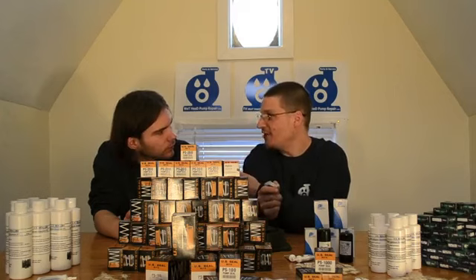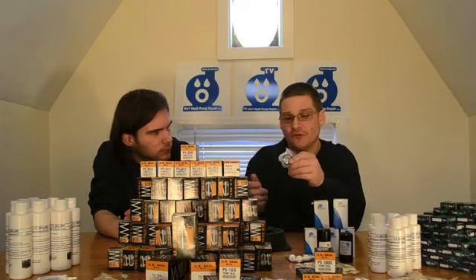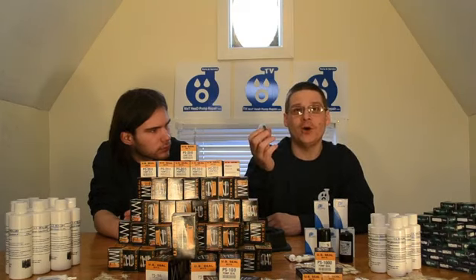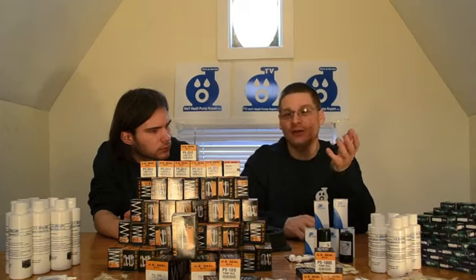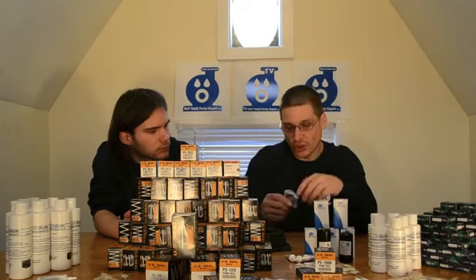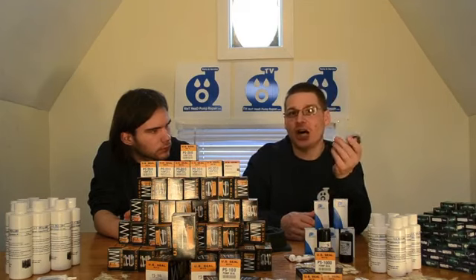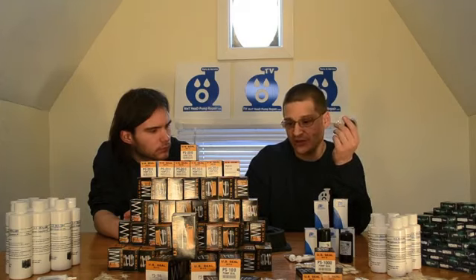Like other videos where I show you how to take the bearings off the shaft — you'll see Robert in other videos taking these bearings off the shaft, and me and Robert putting them on. So if you have a pool pump motor that is making a lot of noise, making a grinding sound, you just need to change the bearings. These bearings are under $20 for two bearings, and with an hour of your time and basic hand tools...